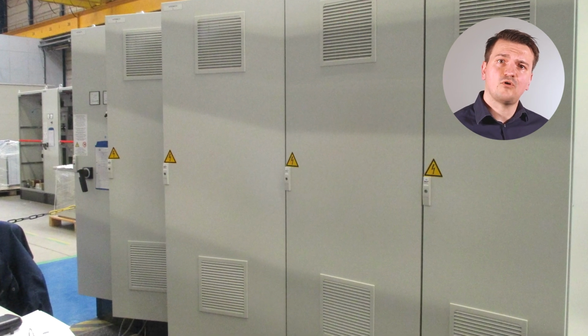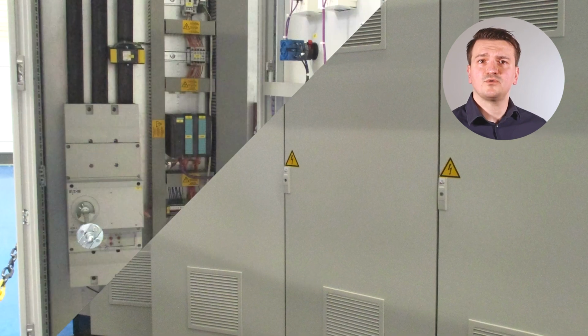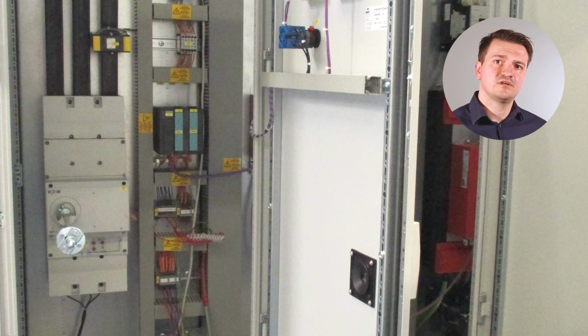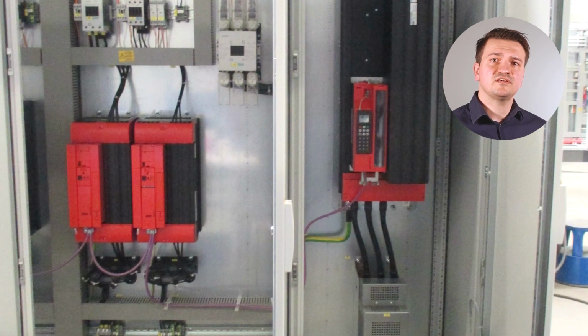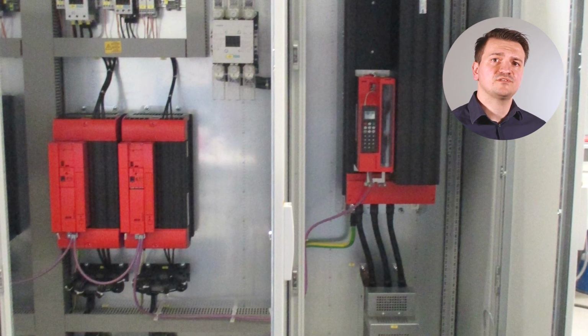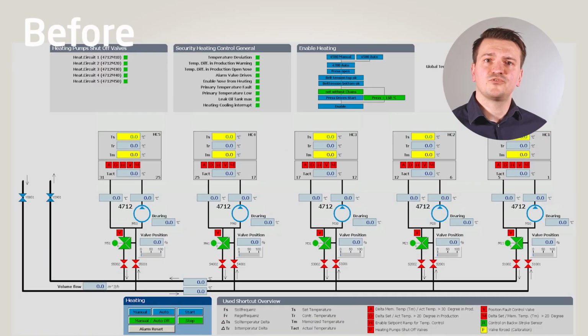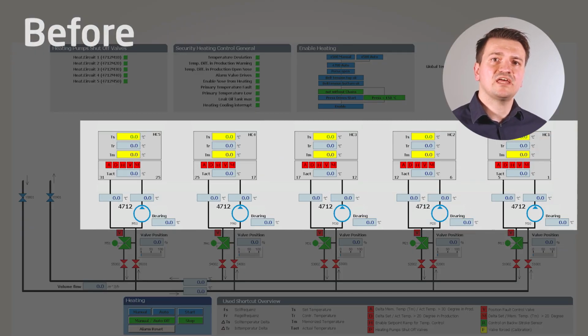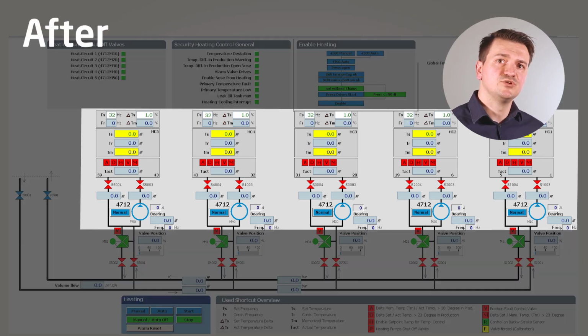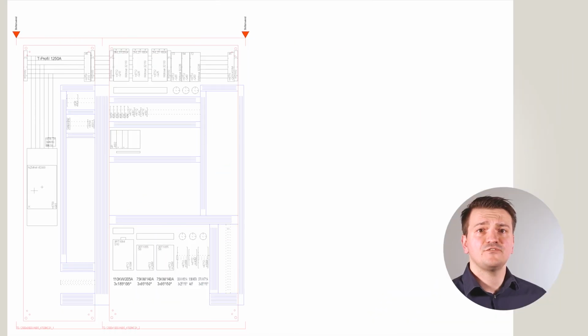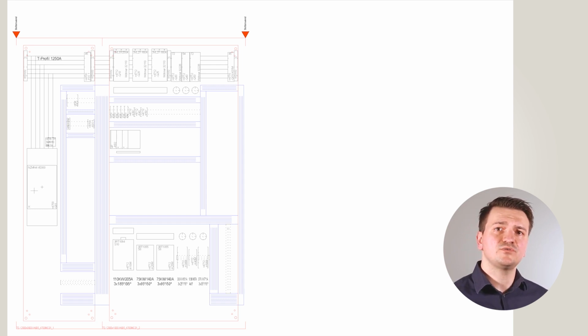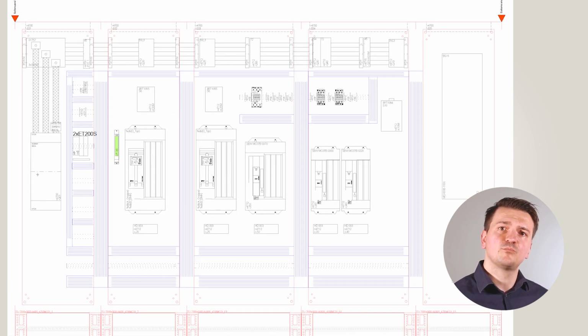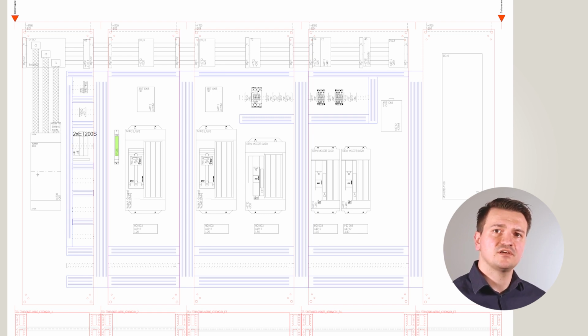This modernization involves optimizing the drive control of the secondary heating pumps. This means that the existing heating pumps will be equipped with frequency converters. The plant software and the HMI system will then be expanded to include the new heating control. And finally, the existing control cabinet will be replaced with a new control cabinet which has already been pre-wired and tested. This new control cabinet can be installed in just a 1-week shutdown.